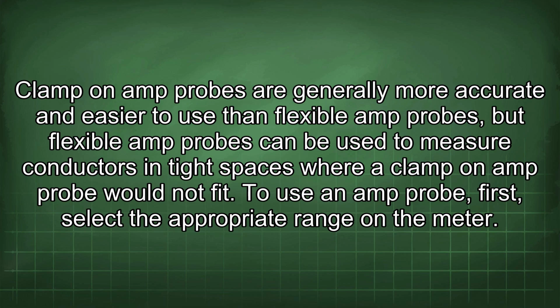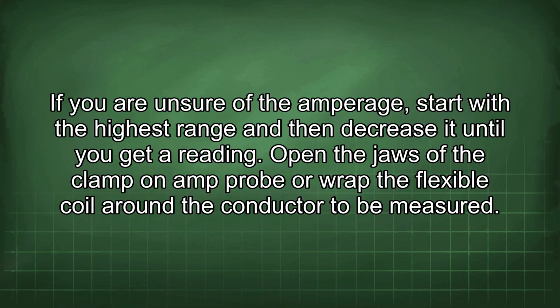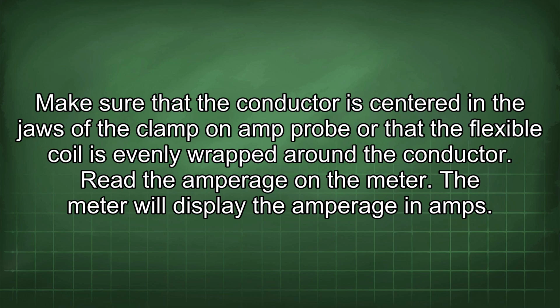To use an amp probe, first select the appropriate range on the meter. If you are unsure of the amperage, start with the highest range and then decrease it until you get a reading. Open the jaws of the clamp-on amp probe or wrap the flexible coil around the conductor to be measured. Make sure that the conductor is centered in the jaws of the clamp-on amp probe or that the flexible coil is evenly wrapped around the conductor. Read the amperage on the meter. The meter will display the amperage in amps.